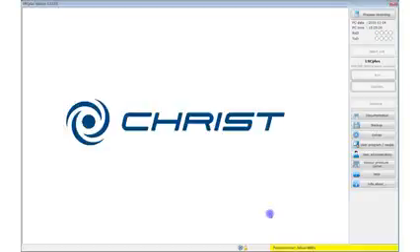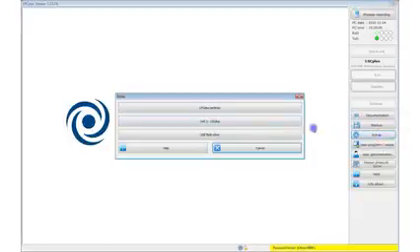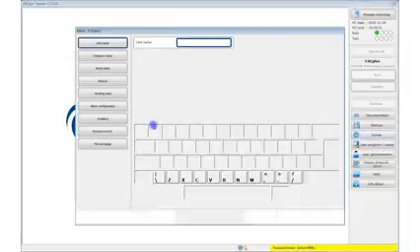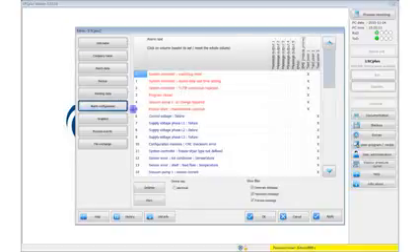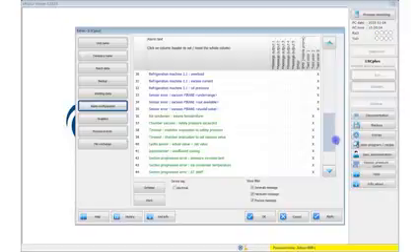The freeze-drying process usually takes a very long time. For many users, it is important to receive messages or alarms immediately, also when they are not in front of the freeze dryer. That is why we integrated user configurable messages and alarms in LPCplus. For example, you can be informed immediately by text messaging on your mobile phone or via email when the process has completed normally or when it is halted due to an alarm. This can easily be configured in the settings window. Emails or text messages can be sent to various receivers.